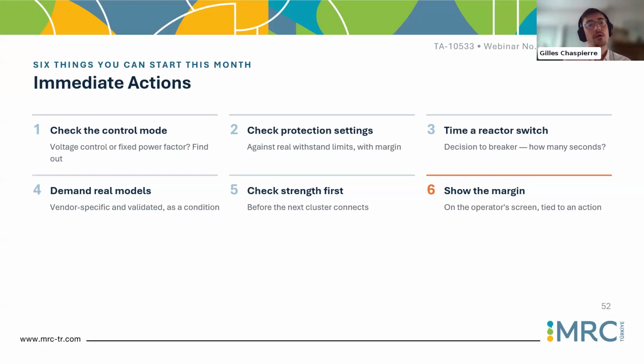That's very important. Then check your protection settings and, regarding your operational guidelines, what is the highest voltage I can face, and make sure that you have sufficient margin so that no asset, synchronous generator or whatever, will disconnect in response to this high voltage, which can be considered normal for the TSO. The second thing to check is also based on the control mode: how much time does it take to trigger a shunt reactor? And probably if it's still a manual operation, it's too slow. So you need to think of what would be the next step. How can I automate this asset and make sure they will be able to connect automatically in case of overvoltage?